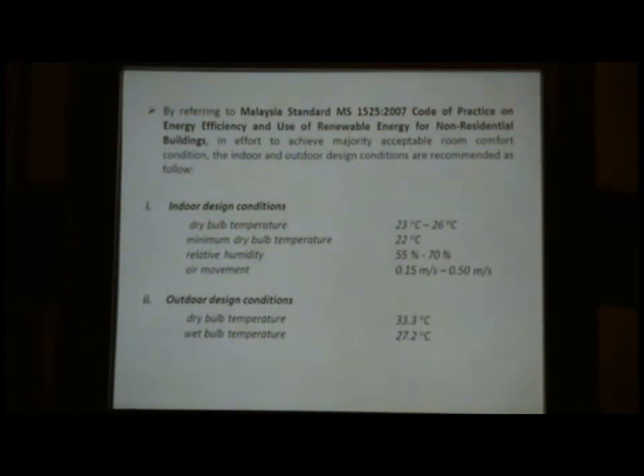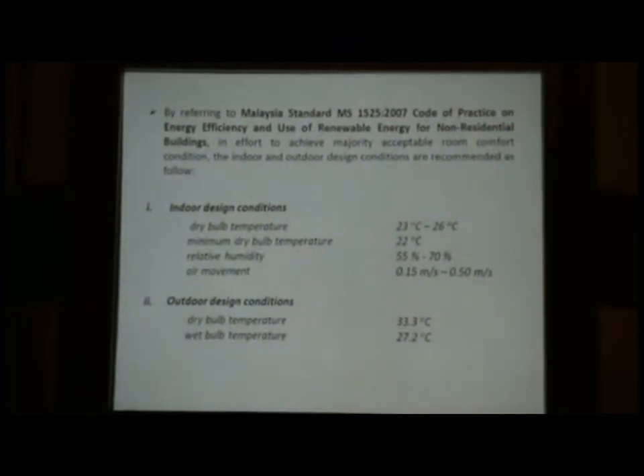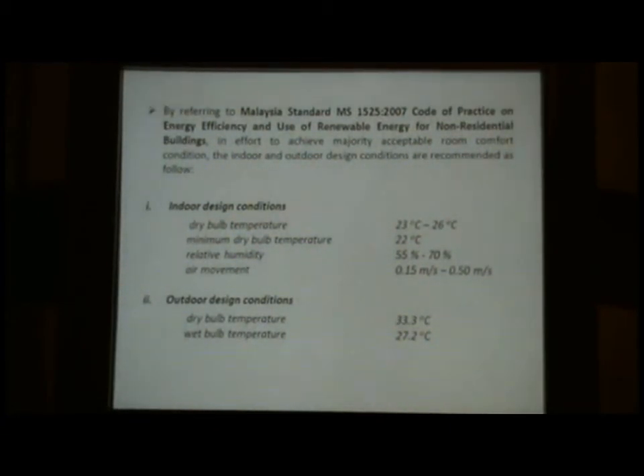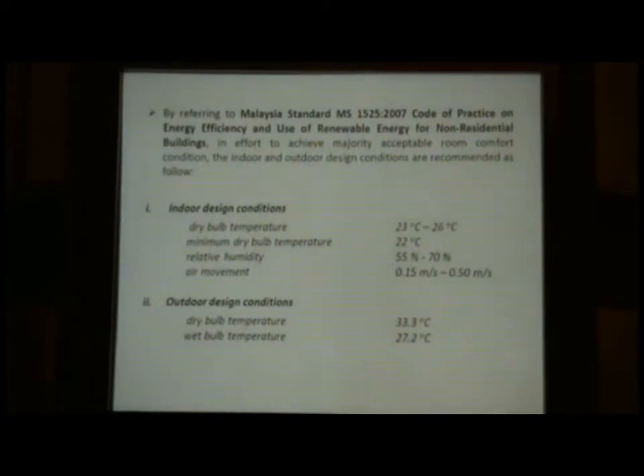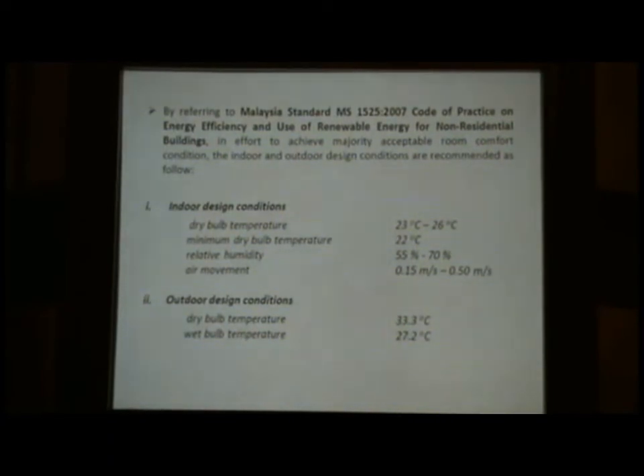Now, air movement. If you look at the standard, it recommends less than 0.2 meters per second. Why 0.5 here? For example, here it is 0.5, which is way beyond the recommended standard. So there are a lot of arguments here, because the more air movement you have, the more energy you have to use. So if you cut it down, you agree, right? In this case, again, there will be arguments. So we have to go back to the scientific research and prove whether Malaysians can accept this 0.5 meters per second, or whether they can accept a lower one.